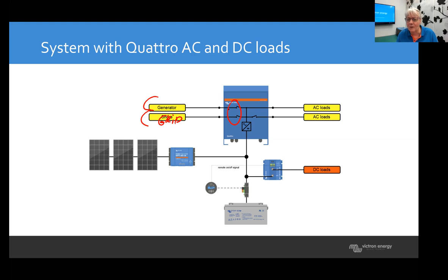You can even do programming with that AC input, so you can say as soon as grid is back, disconnect the generator and connect to grid. You can put logic like that in. It can run two sets of AC loads, or Multis can as well - Multis only have one AC input, but still have this second AC output, AC out 2.